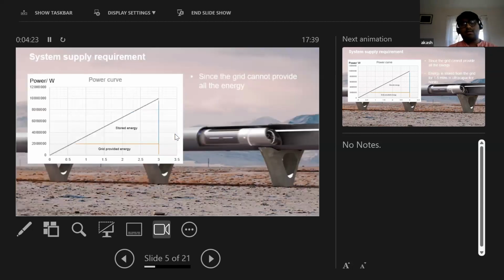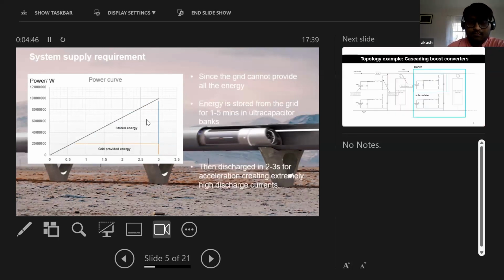This is the power curve I was working with. You need 0 to 10 megawatts of energy in about 3 seconds. 2 megawatts is available from the grid, and the rest has to be provided by stored energy. So energy is stored from the grid into the ultracapacitors in advance by charging for 1 to 5 minutes, then discharged in a short burst of 2 to 3 seconds, which gives extremely high discharge currents into the DC bus.